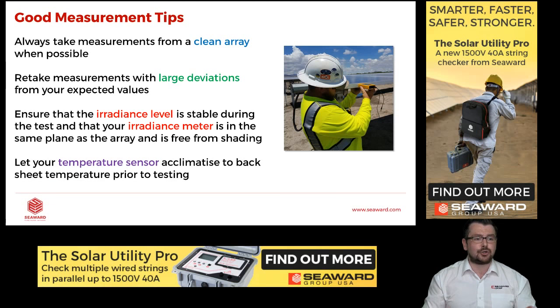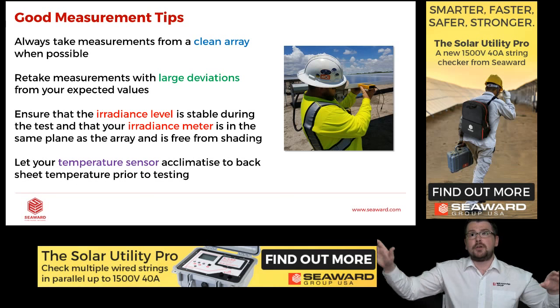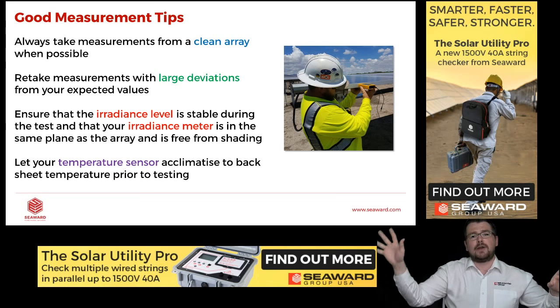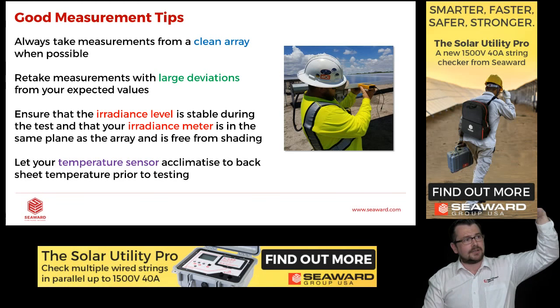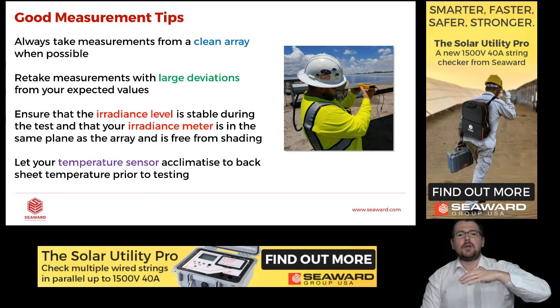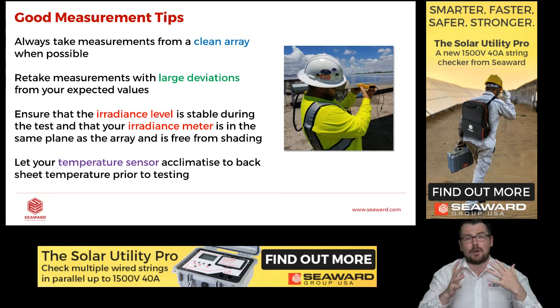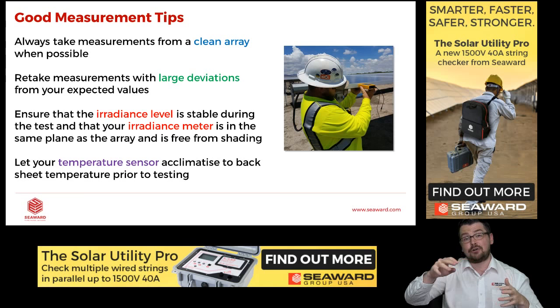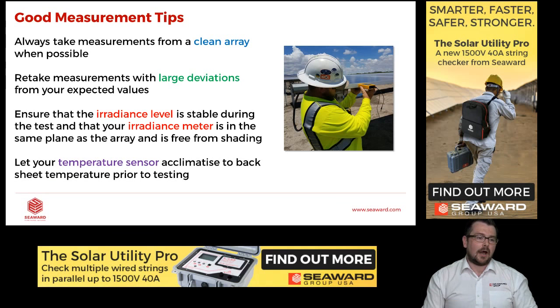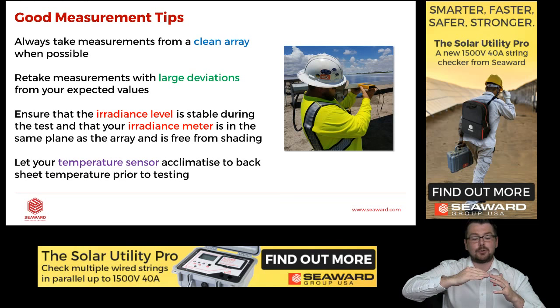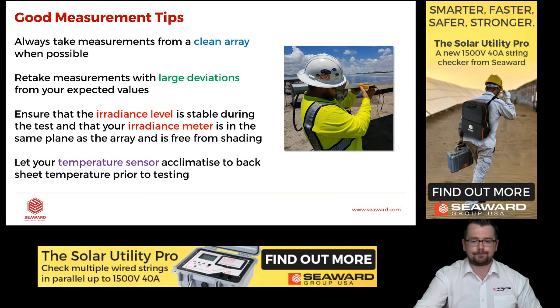We also need to ensure that the irradiance level is stable. So make sure that the clouds are not coming over regularly, that we're not dipping from 900 to 600 to 800. We need a very stable irradiance level when we're testing, because this will make the current level very stable as well. Also let your temperature sensor acclimatize to the back of the panel. Don't just put it on and test. We're actually using a thermocouple, so that thermocouple needs time to acclimatize to the back of the panel.